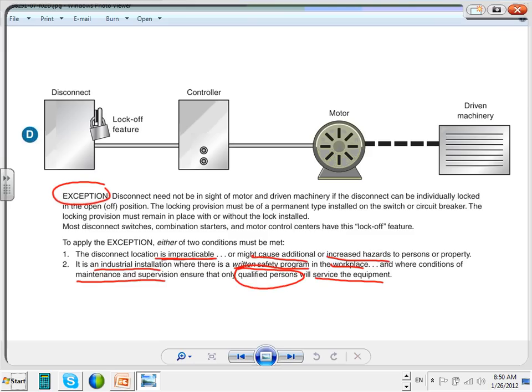So these are where your equipment is locked behind doors, and if you have to do maintenance on that one, you only call qualified electricians to maintain your equipment. Under these circumstances, you can put your disconnect anywhere else. This is common in a wastewater treatment plant, manufacturing. You have their own electricians.